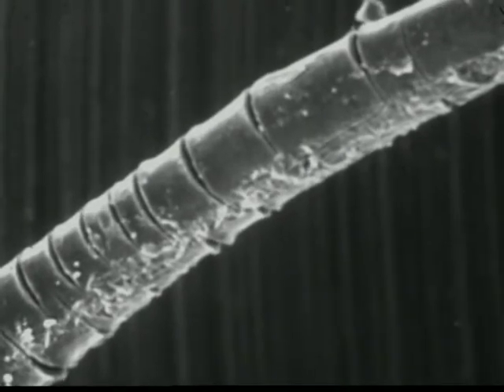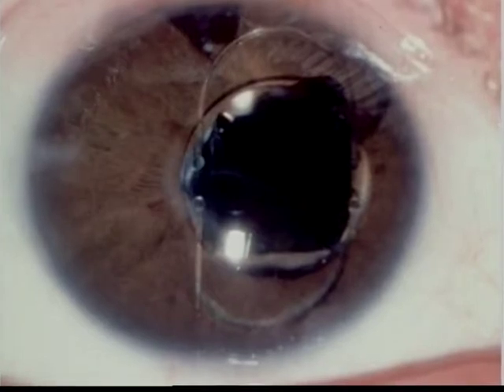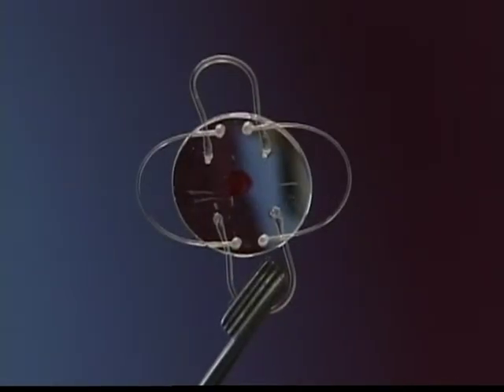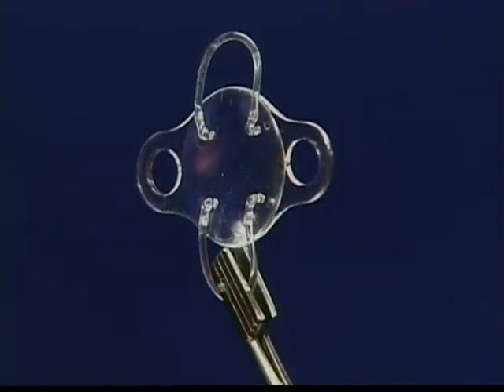Graphically illustrating this are two nylon loops of the same age, one unused and the other explanted from an eye. Binkhorst had also experimented with loops made of platinum iridium, but found it too heavy. The consequences of nylon degradation causing lens displacement were tragic, but especially so when the patients were children. Many surgeons made changes to the basic Binkhorst lens; some of them were probably unnecessary. Fedorov moved the anterior loops 90 degrees, and Jim Little from Oklahoma and Eric Arnott gained greater safety for their lens by making the loops from polypropylene or prolene and placing the optic behind the iris.